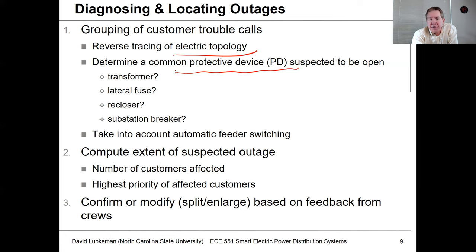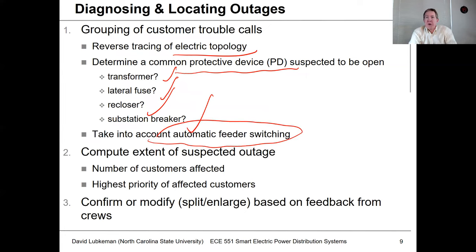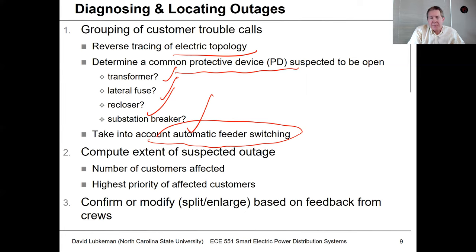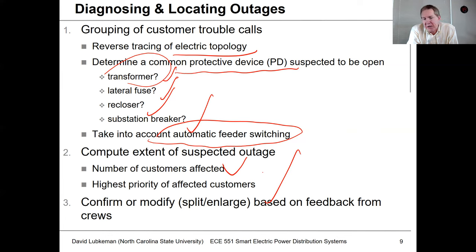We want to see if this is an upstream customer distribution transformer, an upstream fuse, an upstream recloser, or maybe even if it's everybody on the circuit — the substation breaker. We have to be a little smart about this if there's automated feeder switching, because that switching will occur within seconds. Once we trace all the call information to the nearest upstream protection device, we know how many customers are affected and their locations. Based on priority — hospitals, schools, etc. — we then focus restoration efforts accordingly.